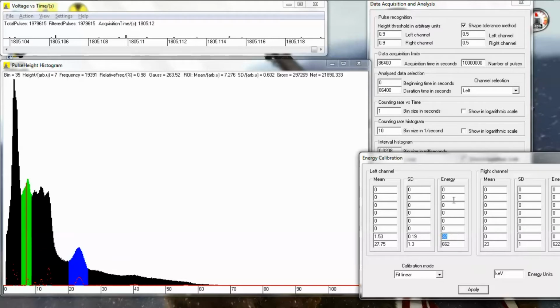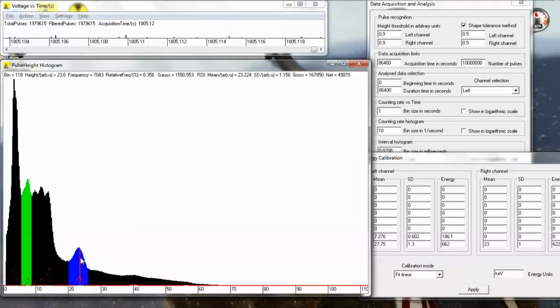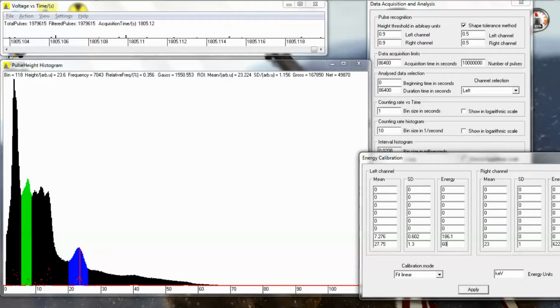Alright, the first energy that we're going to deal with, and this is the energy right here, is going to be radium-226 at 186.1 kiloelectron volts. The standard deviation is 0.602, and the mean of the peak is 7.276. The second energy we're going to deal with is right here, and that's going to be bismuth-214 at 609.31 kiloelectron volts. Its standard deviation is going to be 1.156, and its mean is 23.224. I usually use cesium-137 for this, but this will be good enough. Apply.